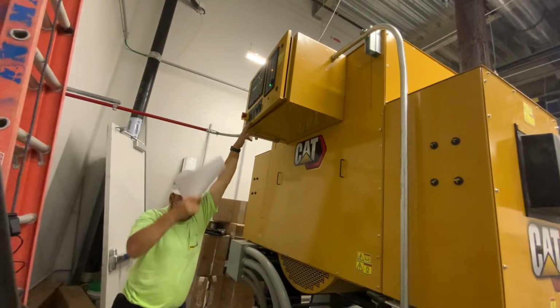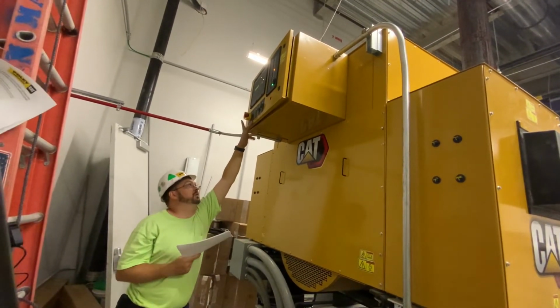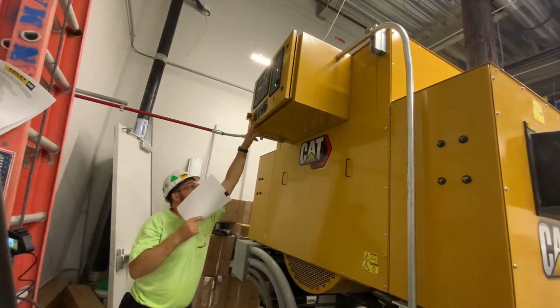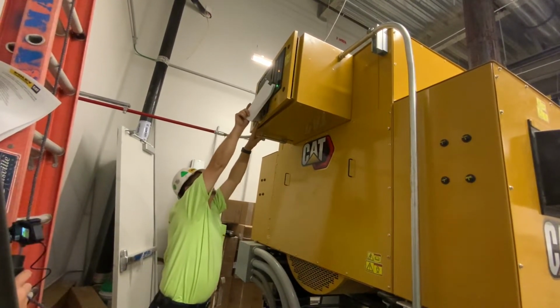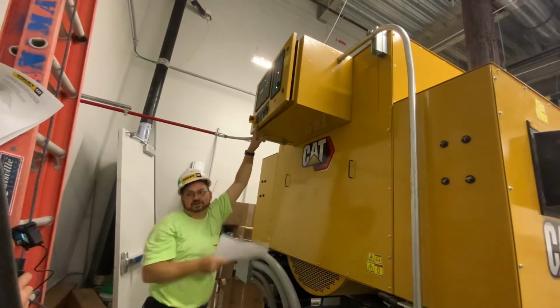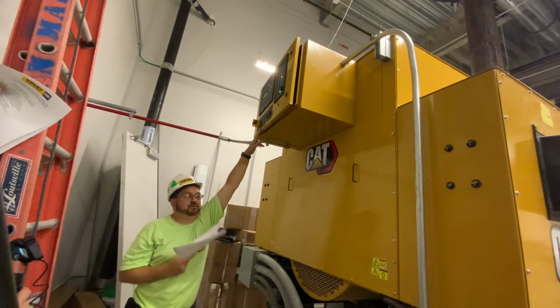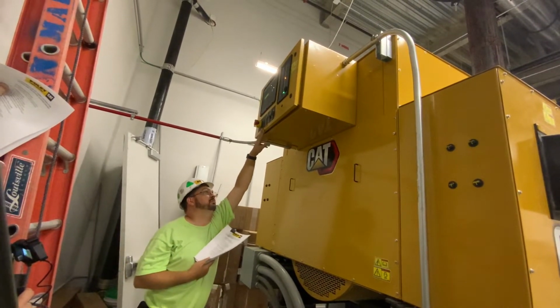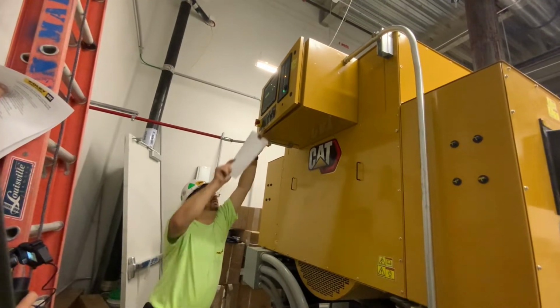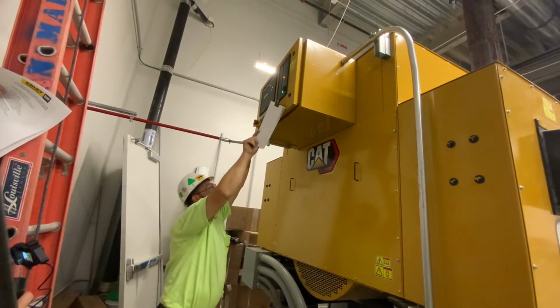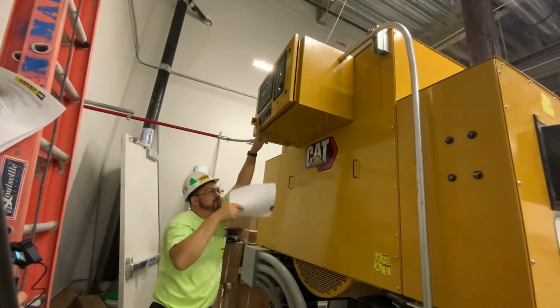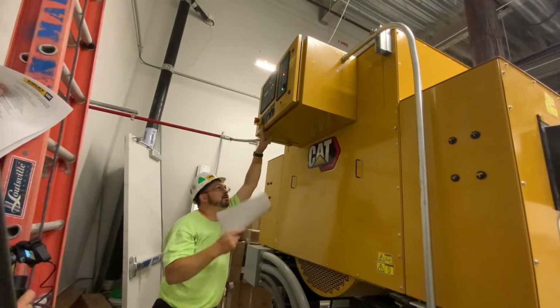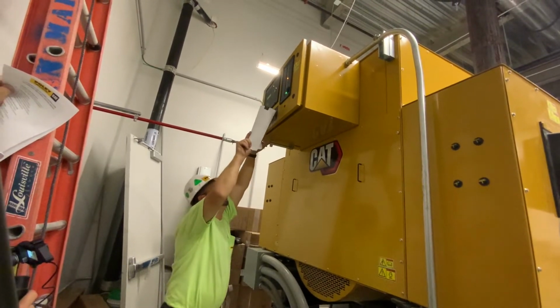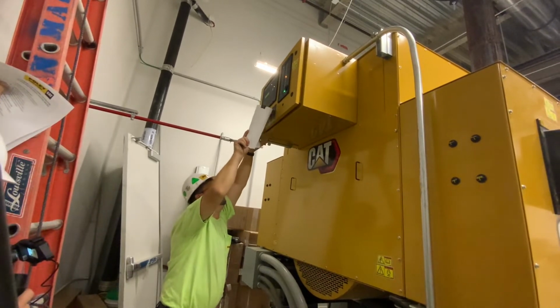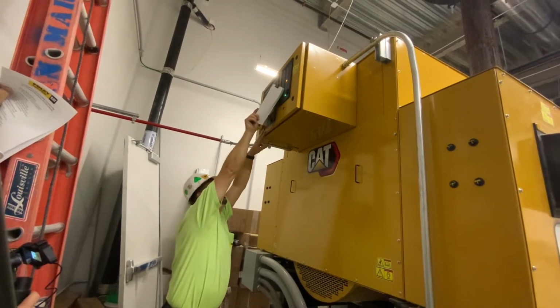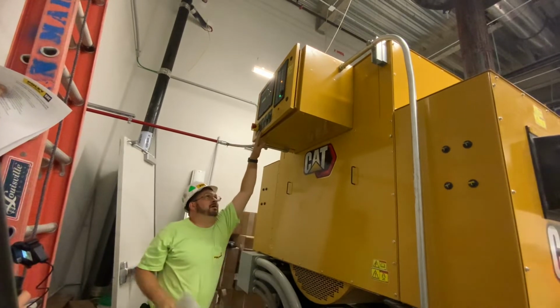So if it was an e-stop, you've got to pull the e-stop back out before you hit that. It will also want the machine not in auto, but put in stop—it gives you an on-screen prompt to put it in stop position before proceeding. After you hit the button, it'll ask you to hit OK to reset all events. You do that, and it'll attempt to clear it. If everything's good, it'll clear, the red light will go off, and you can put it back into auto. The last button up on the right is the event log.